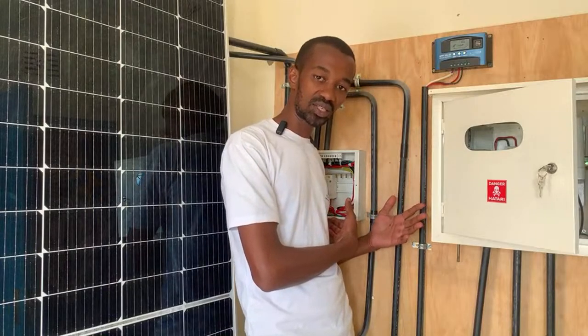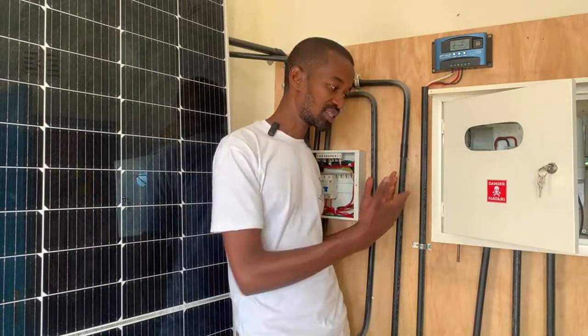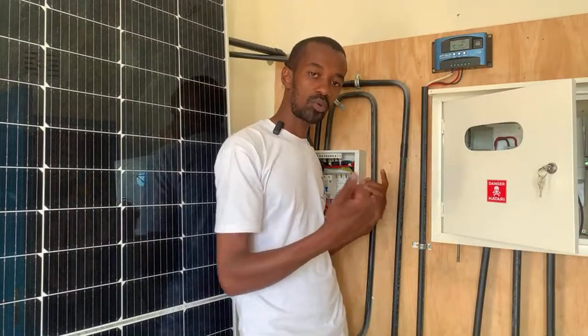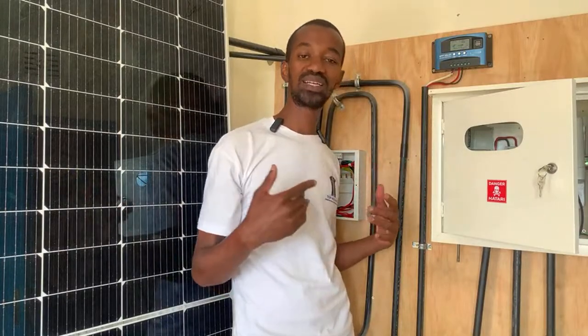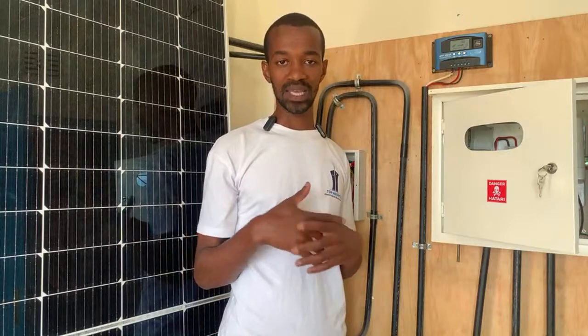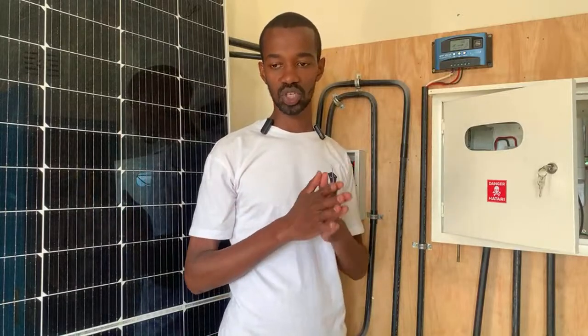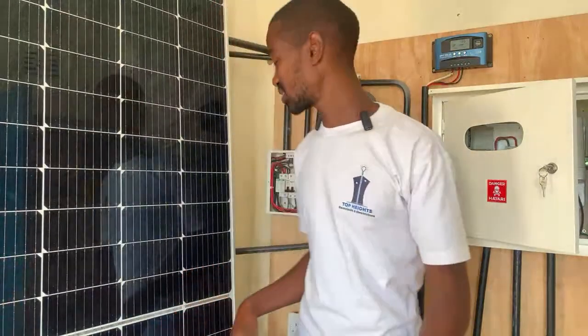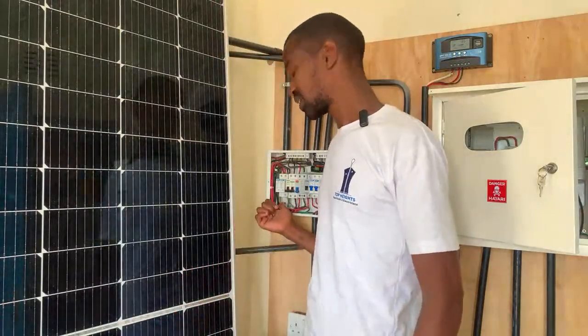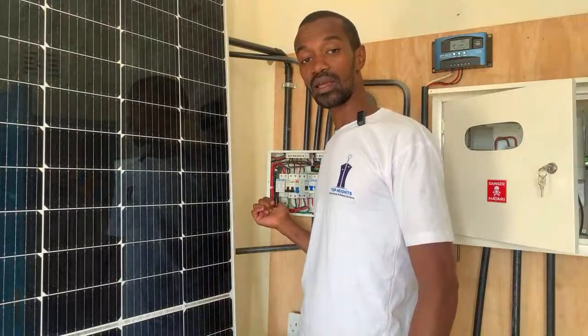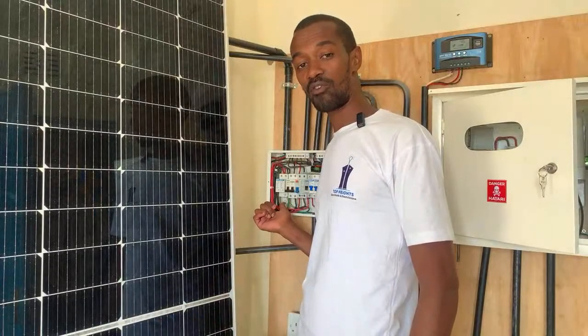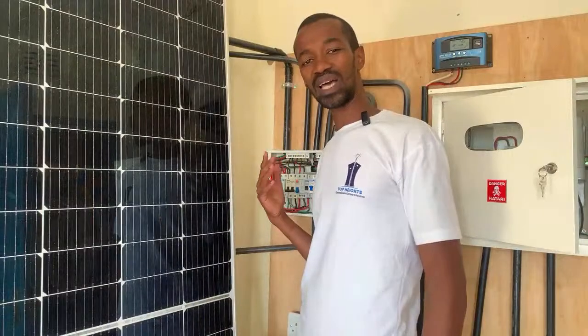Why am I saying so? Because the size of the wire linking the two matters a lot. We normally say it should not be less than 10 millimeter square, in terms of cross-sectional area. But you might ask me, John, if the circuit has factored in the cable size here, we have 4.0, why can't I use a 6?